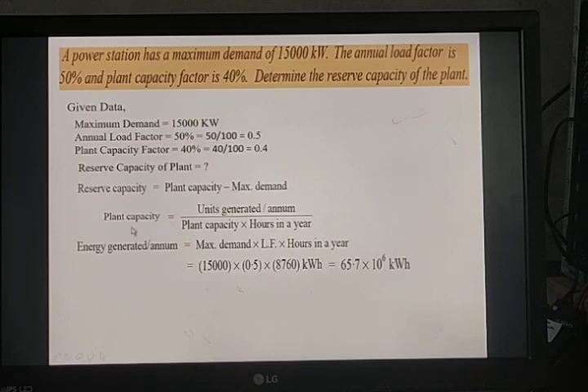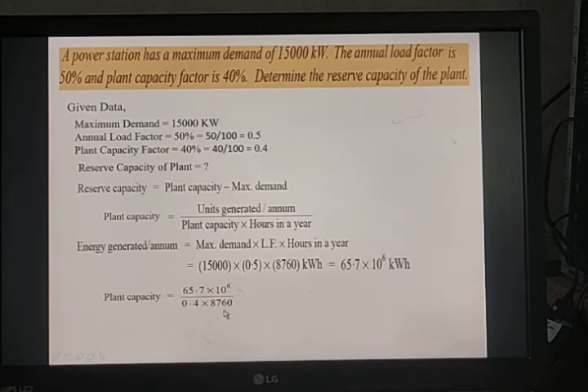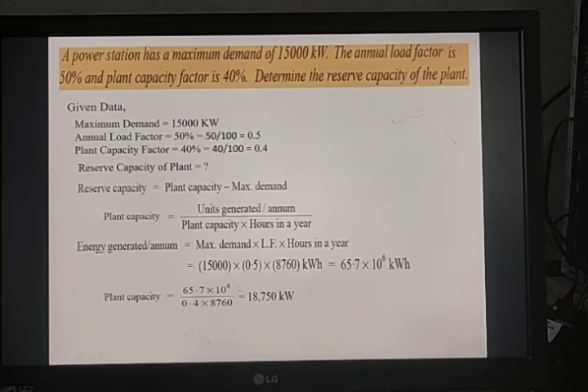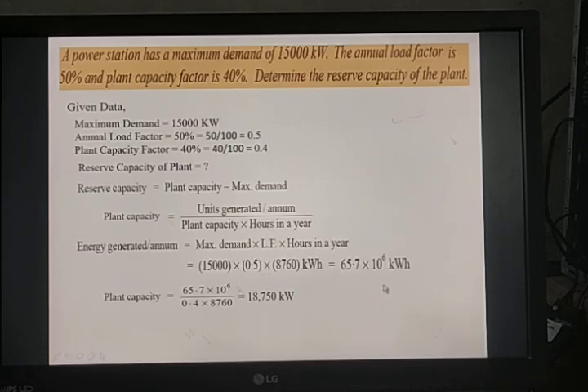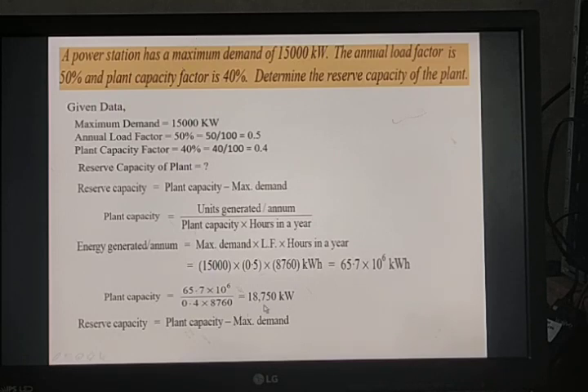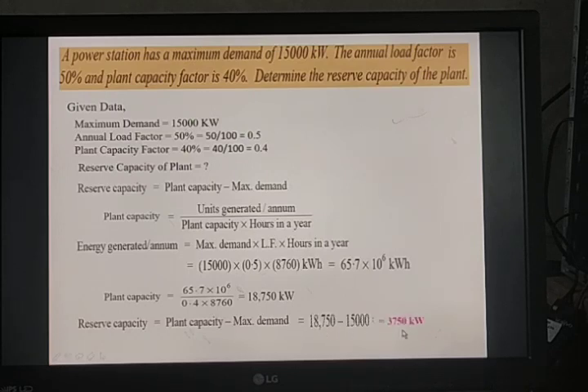Now substitute into the plant capacity formula: plant capacity = units generated per annum / (plant capacity factor × hours in a year) = 65.7 × 10⁶ / (0.4 × 8,760) = 18,750 kilowatt. Reserve capacity = plant capacity − maximum demand = 18,750 − 15,000 = 3,750 kilowatt.